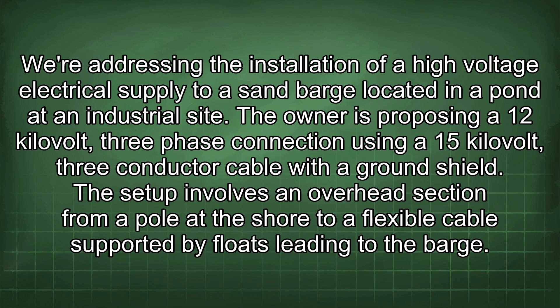We're addressing the installation of a high-voltage electrical supply to a sand barge located in a pond at an industrial site. The owner is proposing a 12 kV, 3-phase connection using a 15 kV, 3-conductor cable with a ground shield. The setup involves an overhead section from a pole at the shore to a flexible cable supported by floats leading to the barge. A transformer on the barge will step down the voltage to 480 volts, which will then feed a 600 amp motor control center, or MCC.